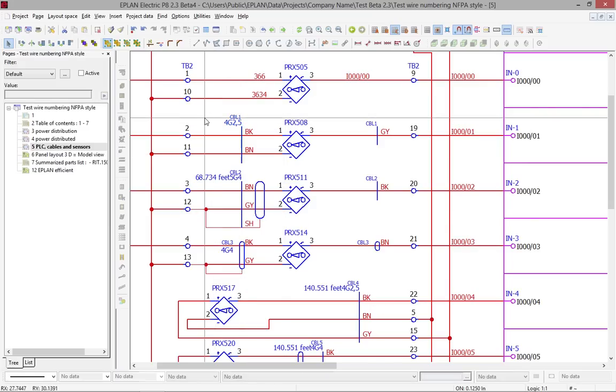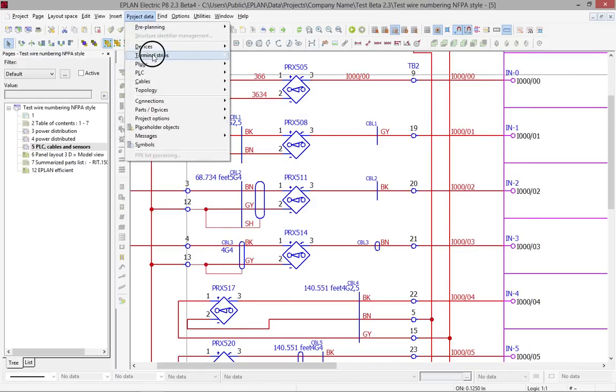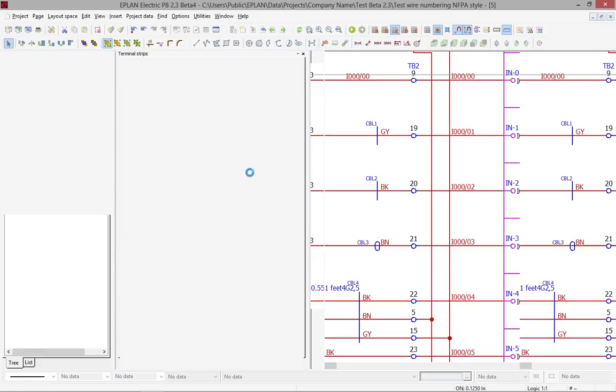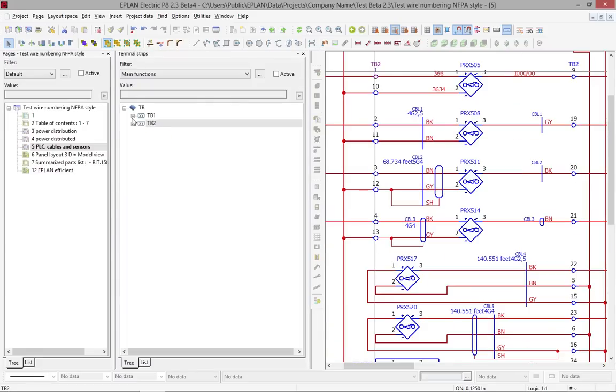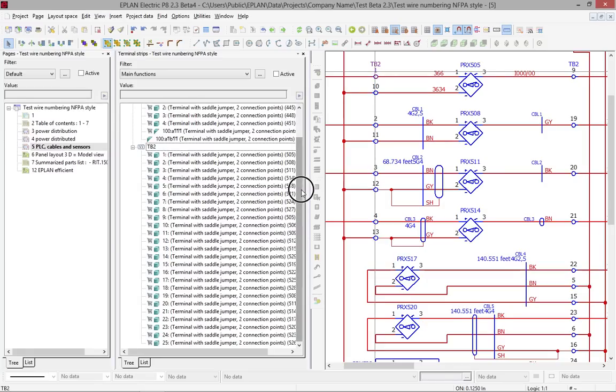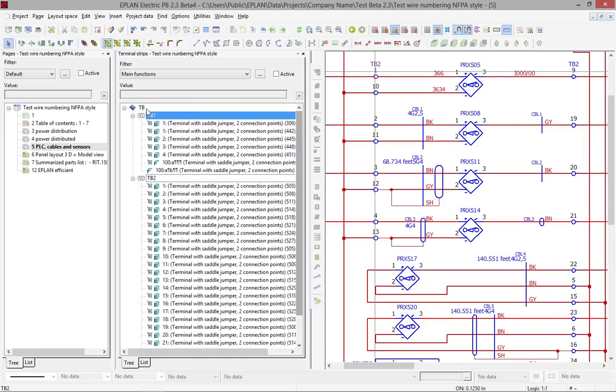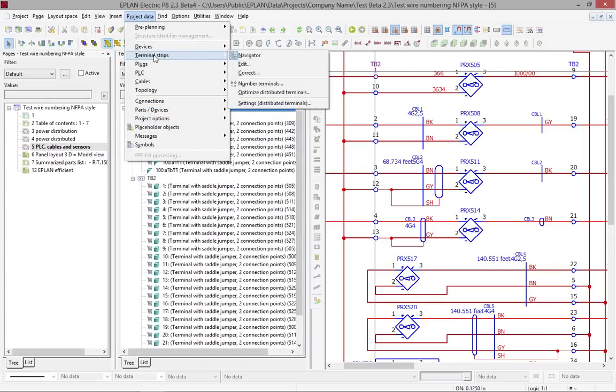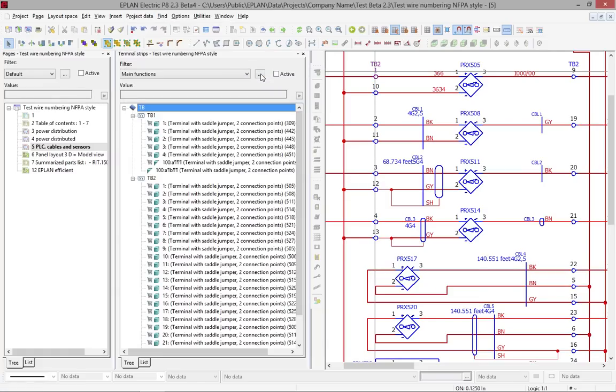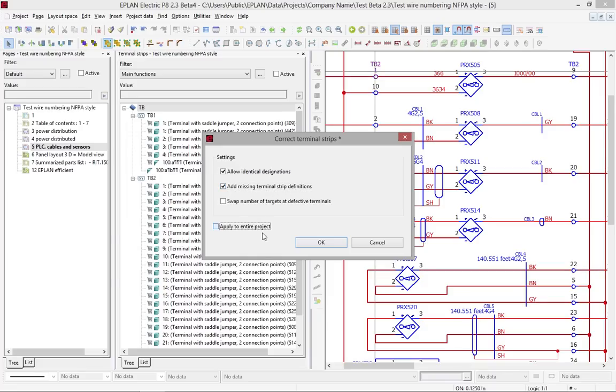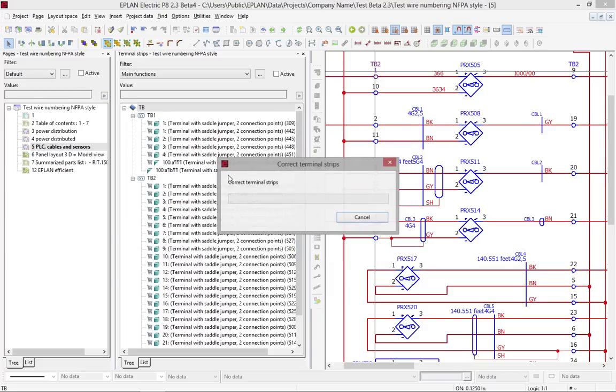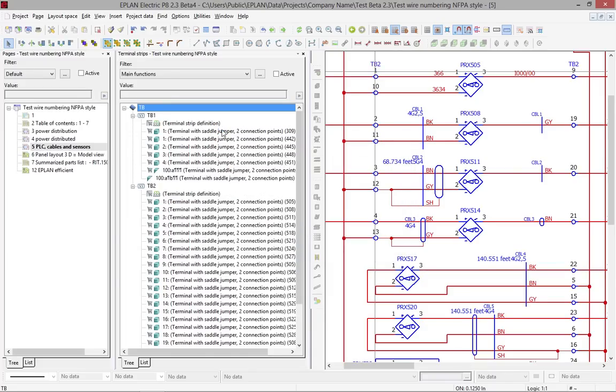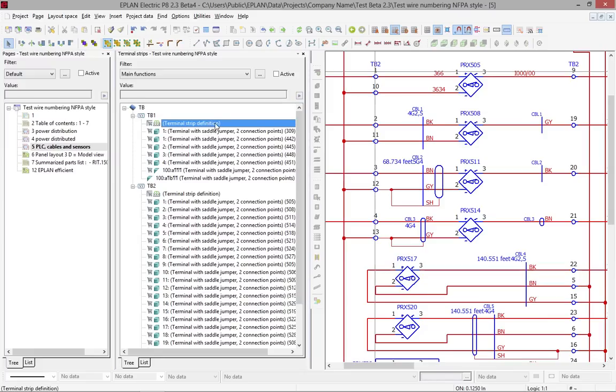First of all, before I move on, I want to check something within the terminals. Within each terminal we have to define a terminal strip definition. If those terminal strip definitions are not there, one easy way to do it is simply by running the pull-down menu Project, Data, Terminal Strip, and Correct. While correcting, it actually adds all the missing terminal strip definitions and this will add throughout your project these terminal strip definitions.